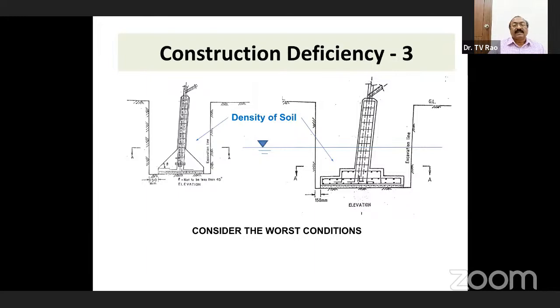That is the task we are doing now, because in some places it is partially submerged, and in some places fully submerged, and in some cases the towers are inundated above ground level more than 1 meter. So the condition changed, and the tower may fail at any moment during rainy seasons because of the wind force. The wind force will be maximum from July to October, so the failure may occur during that period because of the uplift force.